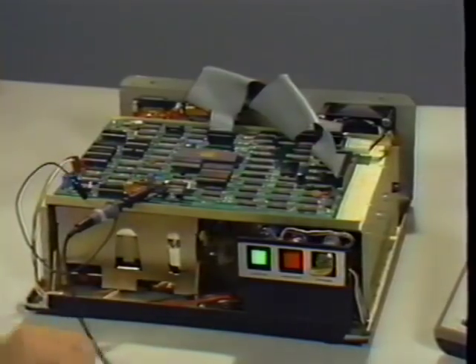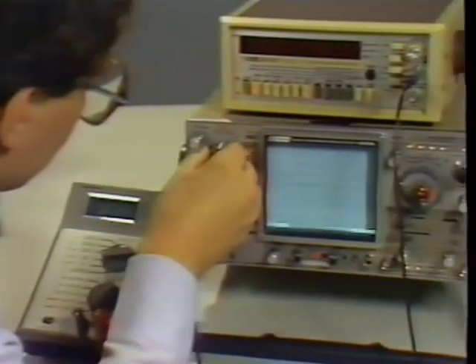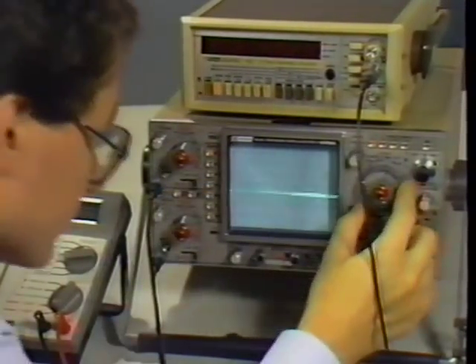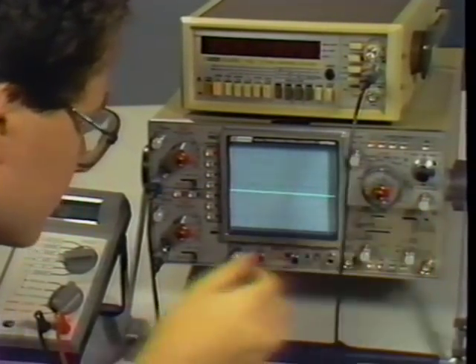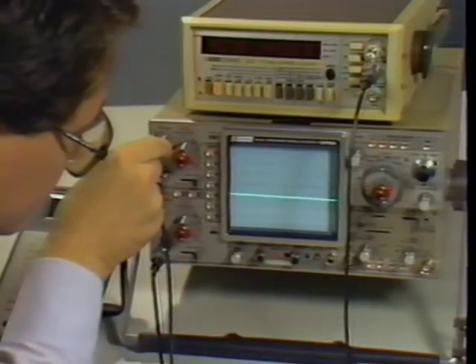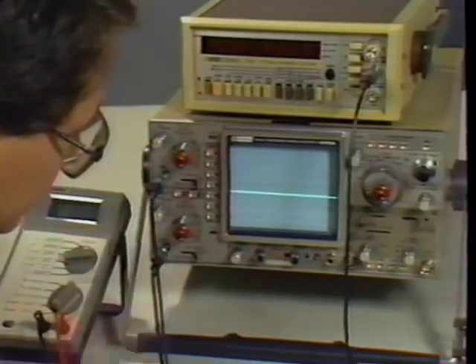The first step is to check for proper voltage on the VCO's fixed bias input. If this voltage is not correct, repair or replace the board before continuing. After verifying this voltage, check the VCO variable bias input and the output frequency. The diagnostic screen gives the test points and correct readings.